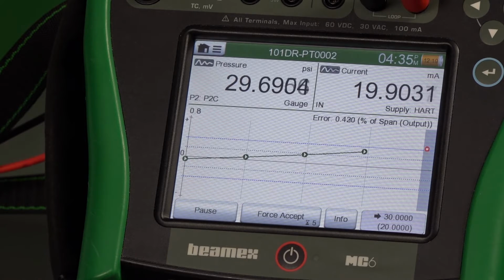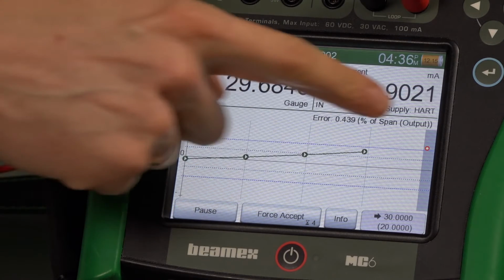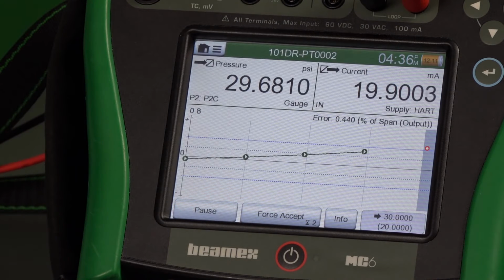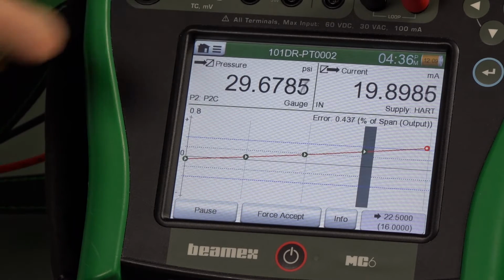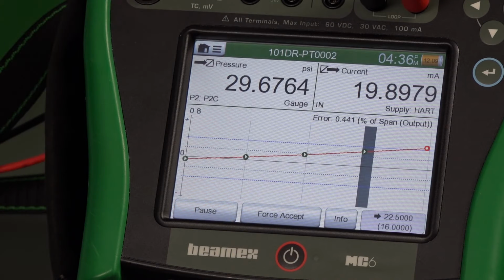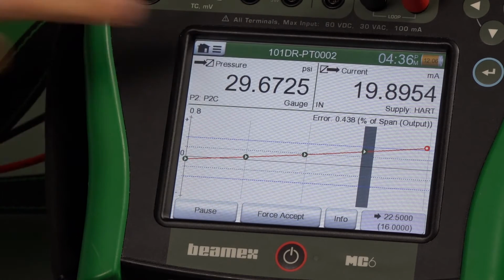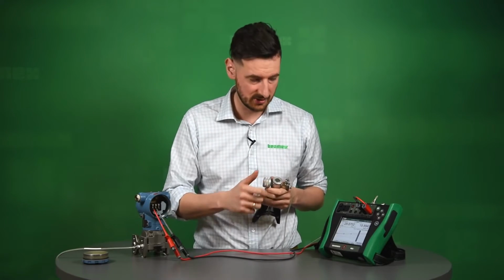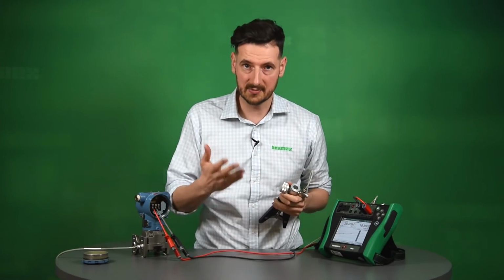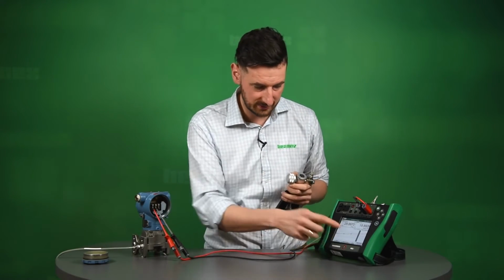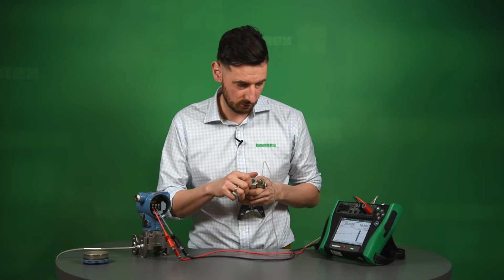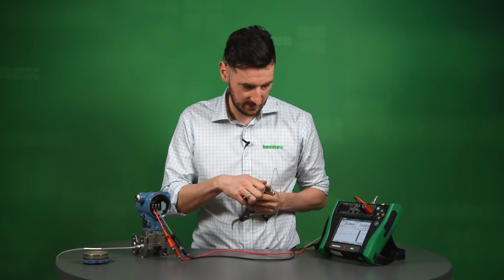Okay, and it looks as if that may actually trend out. You can see that the dot turned red right now. It's actually outside of the tolerance lines, the blue lines. So we right now know that this calibration is going to be a failed calibration. What we have to do right now is obviously capture on the way down. So we have to go right now to 22.5. So we're going to do that now.